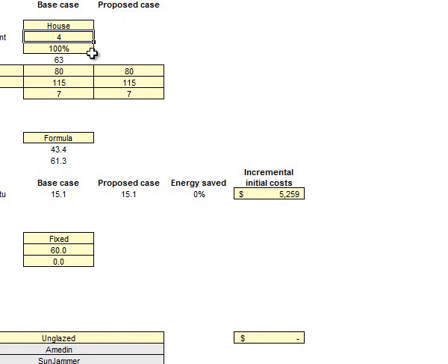We're going to say that they're living in this house 100% of the time, so it's not a rental unit where it's maybe just in the summer months, or a winter cabin getaway type of thing. Then we're going to select typically about 20 gallons of hot water per person per day. The estimated hot water usage, according to RETScreen, is about 63. We're going to up that just a little bit and make it 80, just to be on the safe side. We can make some of these values change as to what we need, but we're going to leave it at 80.